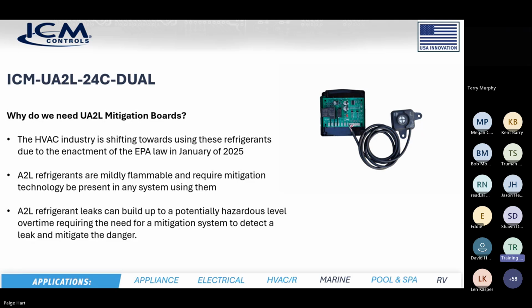So, what happens is, let's say you get a brand new A coil in your furnace and a little leak develops in the coil. If it's a gas furnace, because A2L refrigerant is heavier than air, it's going to settle into the lower parts of the furnace and can be ignited by the gas valve. That could be dangerous if it builds up to a level that supports combustion. So we have to have some type of mitigation system. The HVAC industry is shifting towards these refrigerants, and now it's a law that all new systems as of January 2025 have to have low global warming potential, or A2L, refrigerants.